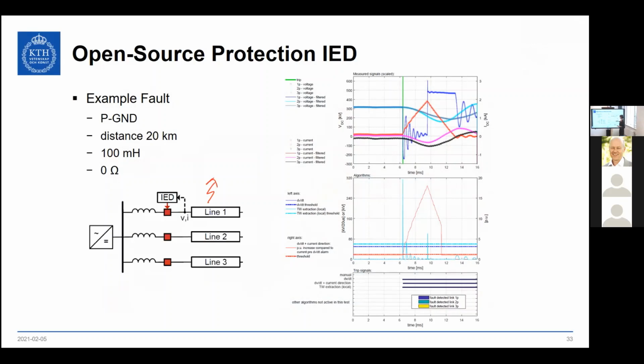In the first window, we see the IED transient fault recorder covering the complete substation, scaled to real system value of 320,000 volts. At this point, you see how, in dark blue, the voltage on the faulted link collapses. You can also see how at that moment the current is rising in this link, and then a DCCB opens and this line is disconnected.